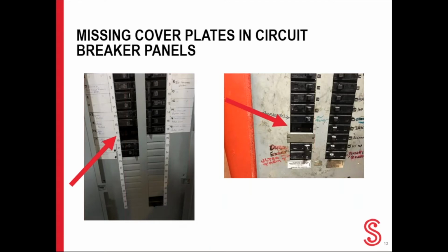So my final section before I get to hand you guys off is actually about missing cover plates located in the circuit breaker panels. So in the pictures, you can clearly see gaps in the electrical circuit breaker boxes. Open gaps in electrical panels or breaker boxes are an electrocution and fire hazard exposure. The business should install cover plates in these electrical panel boxes to make sure the gaps are properly sealed off. The cover plates will help prevent bodily injury from electrical contact and electrical shorts or sparks from igniting surrounding materials.